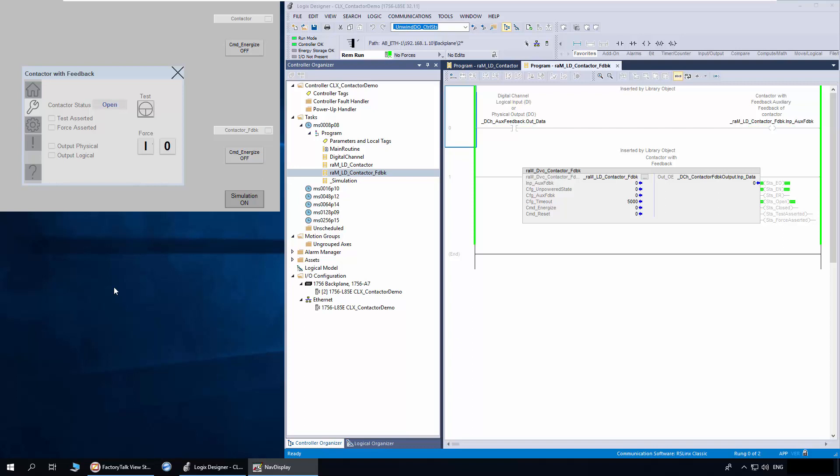The user can also force the contactor output using the force buttons. Once forced, the contactor will remain forced until it is released from the faceplate. The spanner icon on the navigation object indicates if the contactor output is forced. Both force and test do not impact the logical output of the contactor. Thus, the contactor can be put back to user logic control once the force or test is removed.